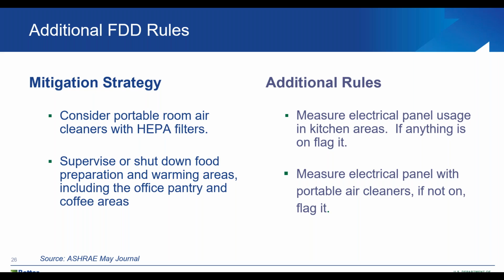So additional rules, we mentioned one with UVC need to be created, but ASHRAE also recommends other things. Well, maybe you're installing portable room air cleaners with HEPA filters. I've seen a lot of these on energy audits I've been doing recently. People are buying these portable cleaners and they use a certain amount of energy. Well, are people in the space or not? Do they actually need to be operated?